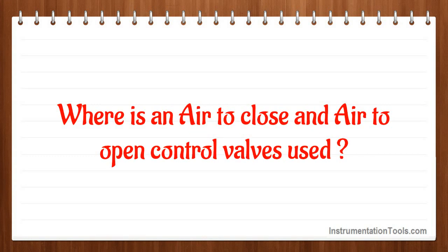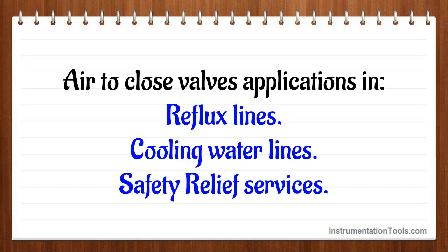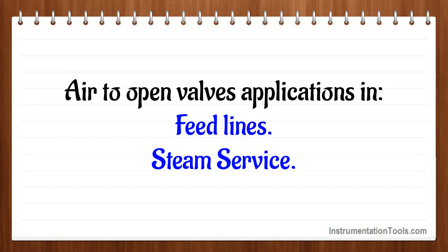Where is an air-to-close and air-to-open control valve used? Air-to-close valve applications include reflux lines, cooling water lines, and safety relief services. Air-to-open valve applications include feed lines and steam service.